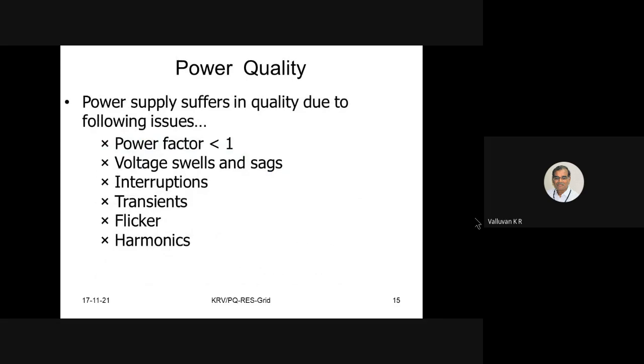Power supply suffers in quality due to the following issues. Power factor, we are all very much familiar with, because this issue started the moment we started using alternating current, but now it has become a fairly simple issue to sort. Voltage swells and sags, that is, voltage going up above the rated value, and voltage dips, sags. Interruptions, meaning power cuts. Transients are small surges in the power line, unnoticed by the human eye. Flicker, like we have seen a tube light sometimes flickers. And harmonics. These are all big problems which create both technical and commercial losses to society.